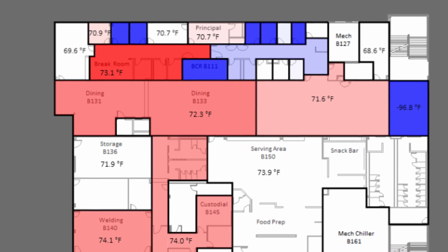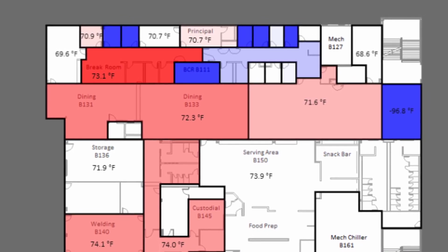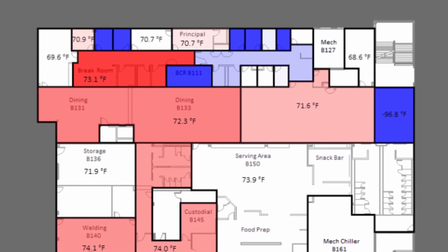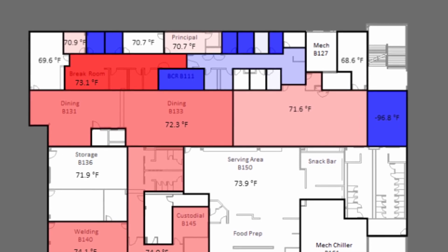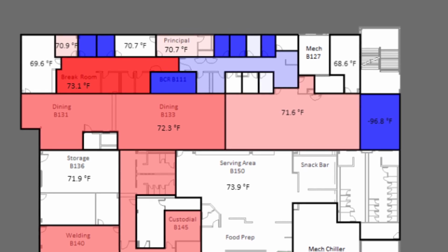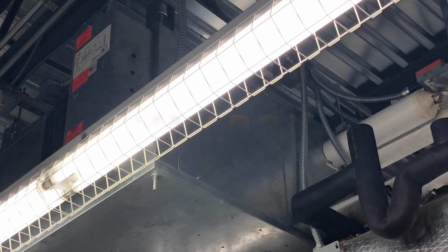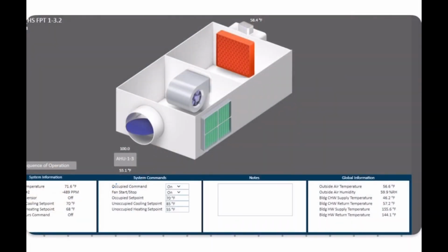So now we're looking at a specific area, and we're gonna go deeper into this and look at a specific room and see how this room is gonna start cooling through the cooling tower and the centrifugal chiller. Okay, so what we're looking at now is the VAV box, and I'm gonna show you how this operates. This is a VAV box, and this is how you cool down a specific room, or sometimes even an area, a hall, like I said, or any room. So right now, let's look at this. Here is our heating, which we're not gonna talk about, but that's how you provide heating from the boiler. So how do you provide cooling?